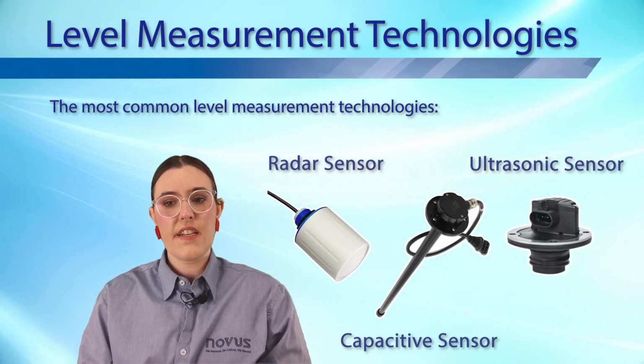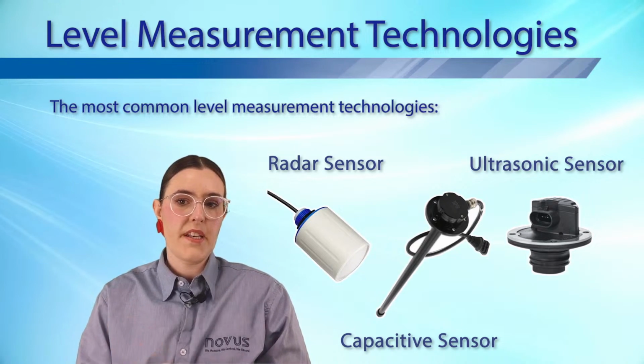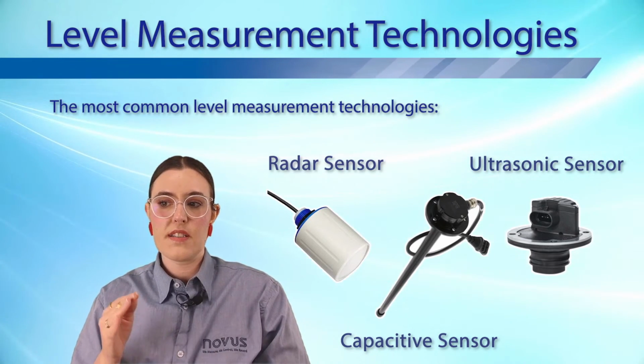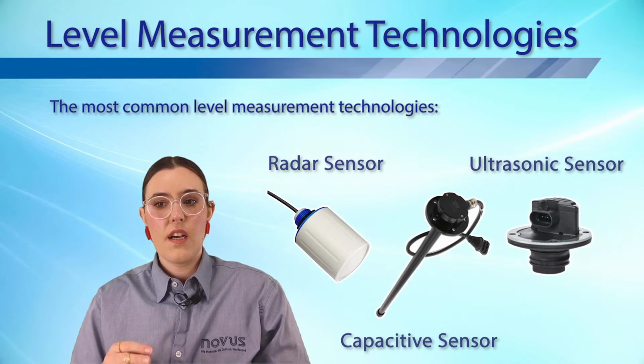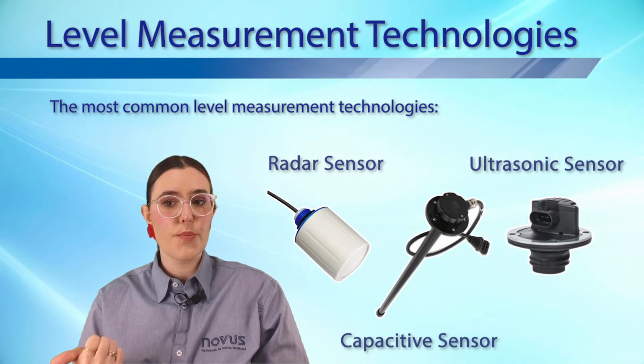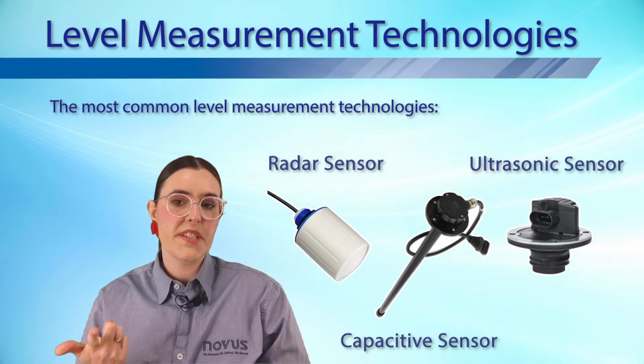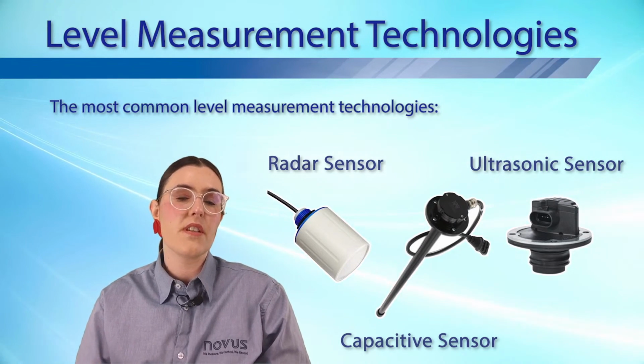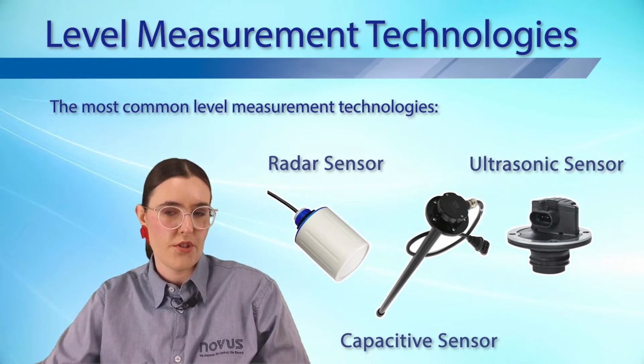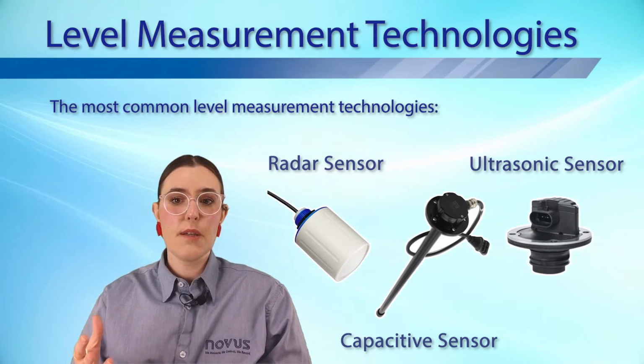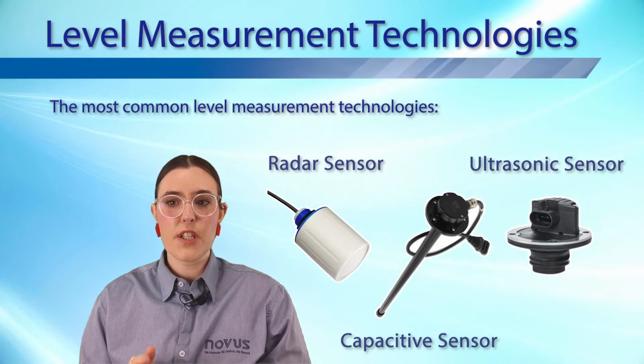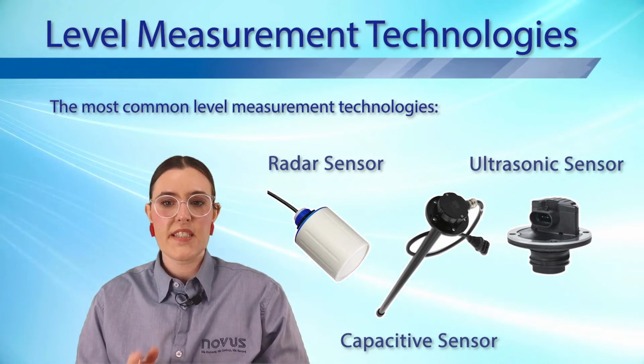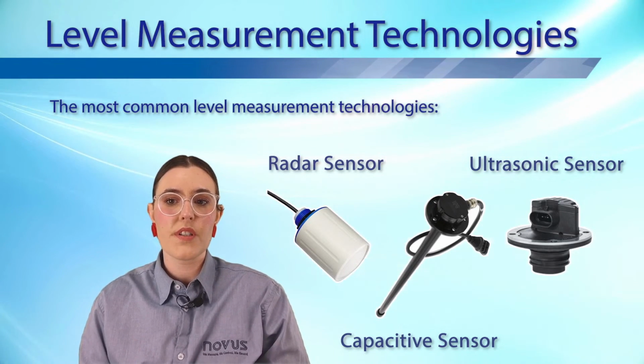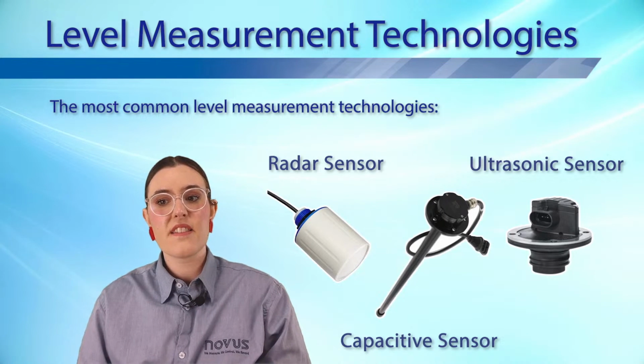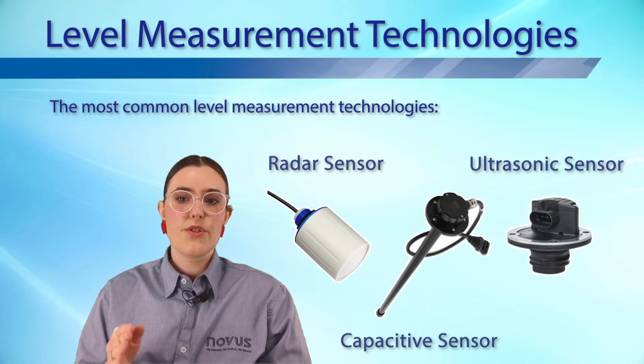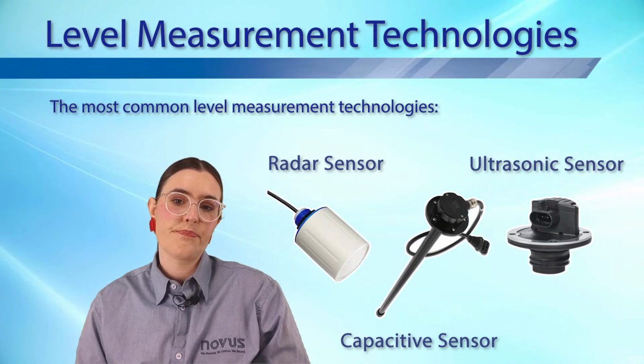So the designer or the project manager needs to choose a level sensor according to the type of material to be measured, the container where the material is stored, and the budget available to execute the project. For example, capacitive sensors have the lowest acquisition cost, but installation requires more work since they are invasive, and the sensor rod needs to be cut to fit the height of the tank.